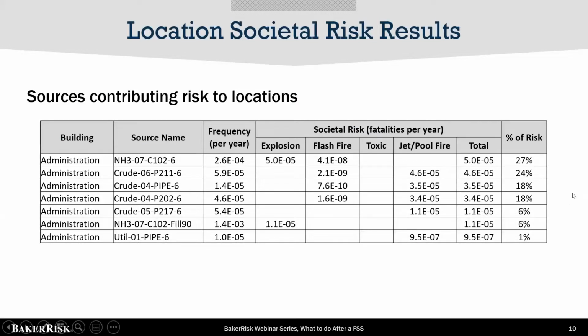In this example, an ammonia source from C102 causes 27% of the risk to the admin building, predominantly from explosion hazards, followed by the crude P211 source representing 24% of the risk, predominantly from jet pool fire hazards. These two scenarios represent over 50% of the risk to the admin building. So instead of looking at refinements at the admin building itself, you could go back to the source and identify risk refinements and mitigation strategies associated with these sources, which would also mitigate and refine the risk to the admin building.